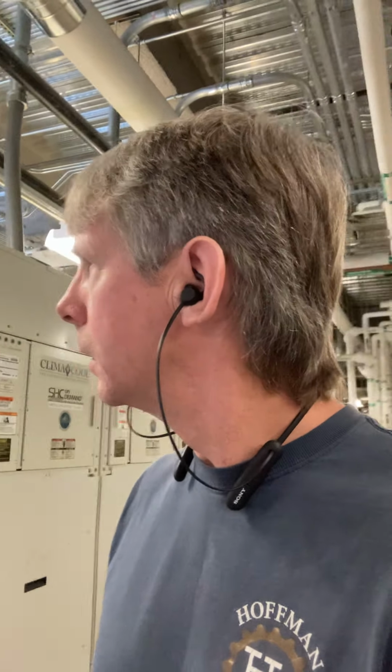for a design day, which is a hot day, would be like a 10-degree temperature rise across those coils. So if we're putting 44-degree water into the building, we would expect to see something like 55-degree water coming back to the chiller. So these chillers then are going to stage up compressors so that we can bring that temperature back down to a leaving 44-degree set point.